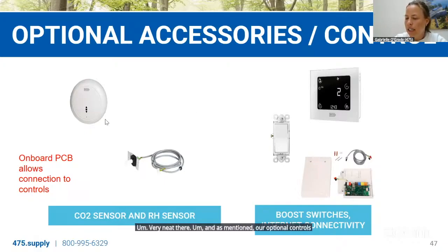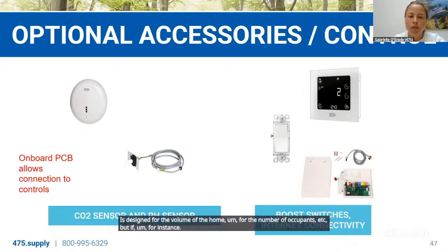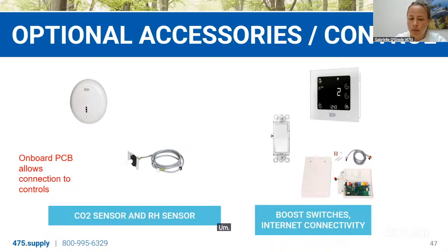We have the CO2 sensor here, so you can have the system ramp up. Most homes don't need this because it's pretty set and forget it, and the system is designed for the volume of the home, for the number of occupants, etc. But in our office, for instance, we use it because we have variable occupancy rates. And so as more people come in, the system ramps up as needed. So it ramps up and ramps down.